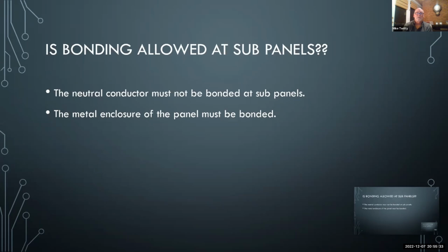So that's two different means of bonding. You bond the metal can always. Any metallic enclosure gets bonded. But the neutral does not get bonded to that panel like we showed in the previous slides as it does in the service equipment. That's the difference. So understand that when you just say you can't bond a sub panel, well, you have to bond a sub panel to keep the continuity of the metal connected to the other equipment in the home.